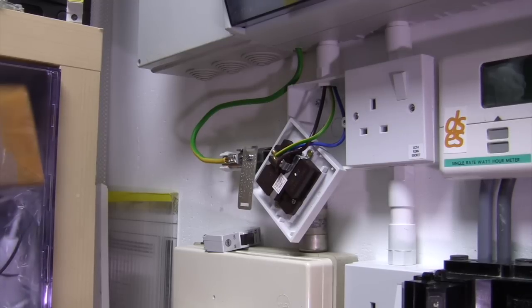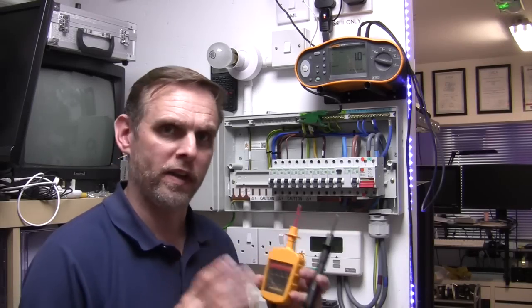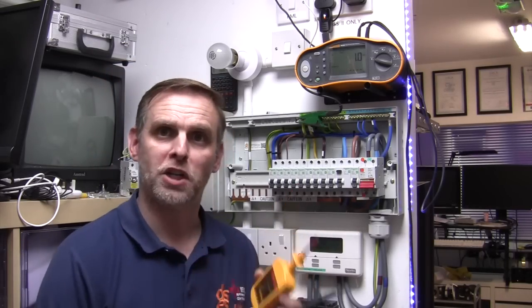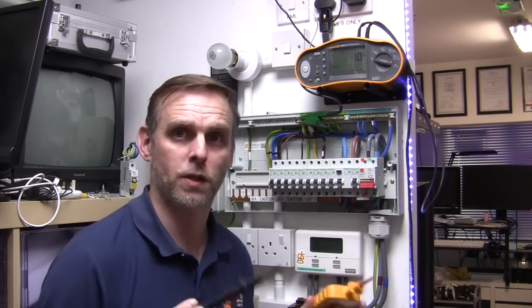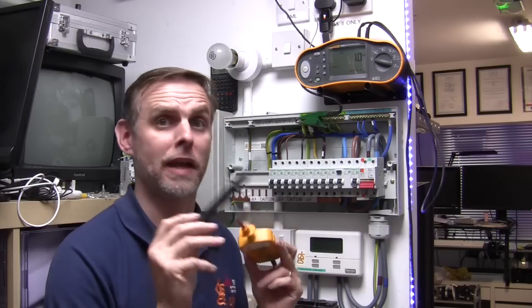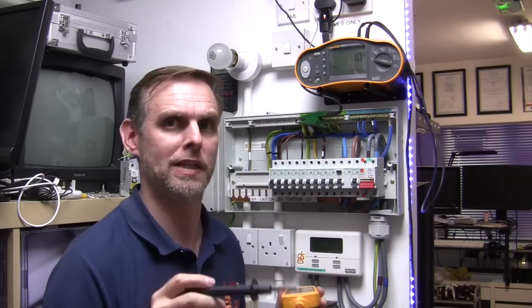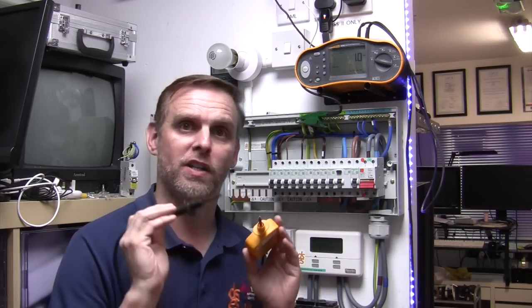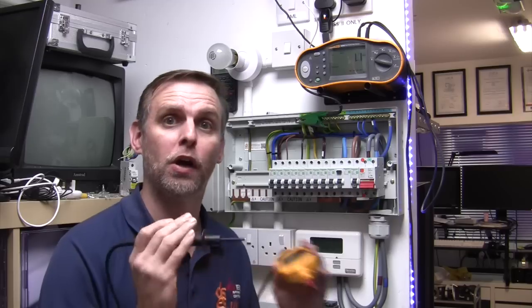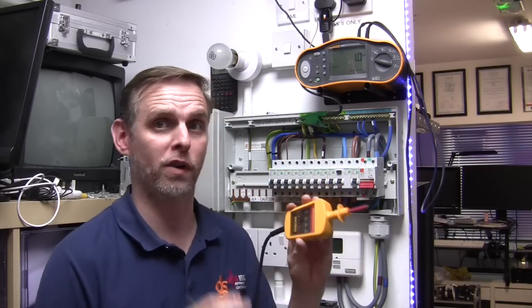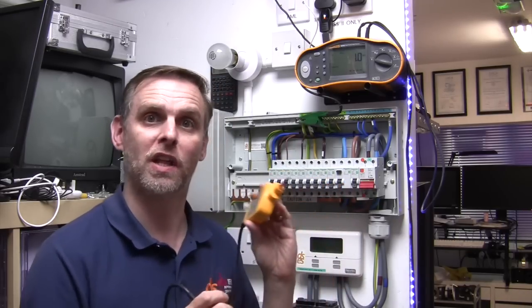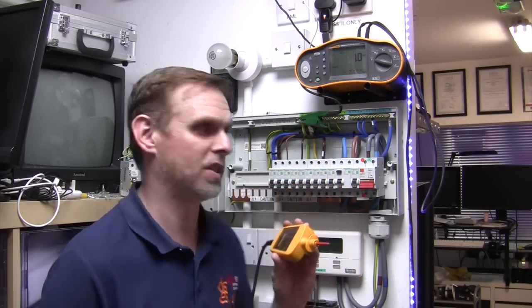when I start work. One other thing to mention about applying your voltage indicator's probes is to always place the first probe, often coloured black and labelled as the negative probe if your indicator supports DC, onto the non-line part of the circuit, i.e. the neutral or the earth, before placing the second probe, often coloured red and labelled as positive, onto the line or suspected live part of the circuit.